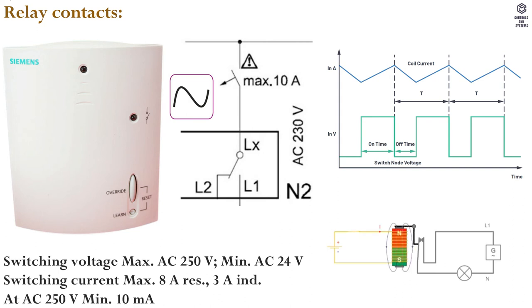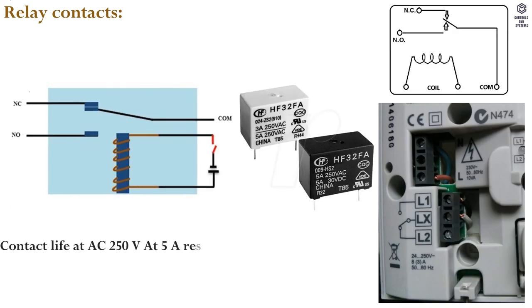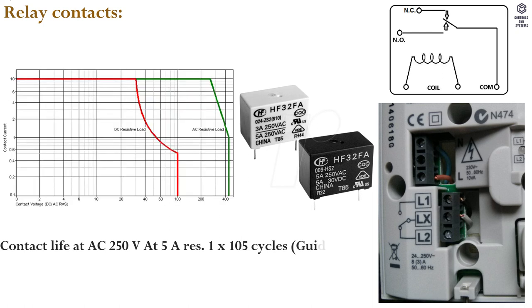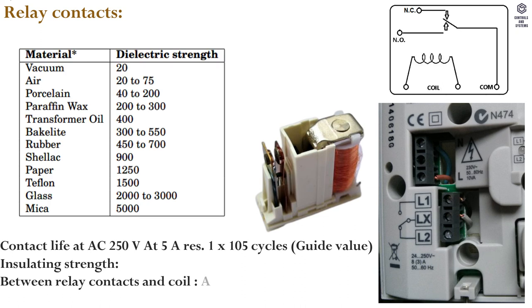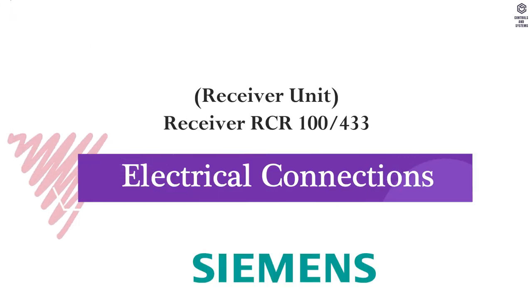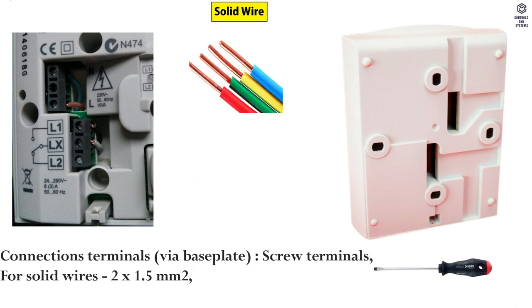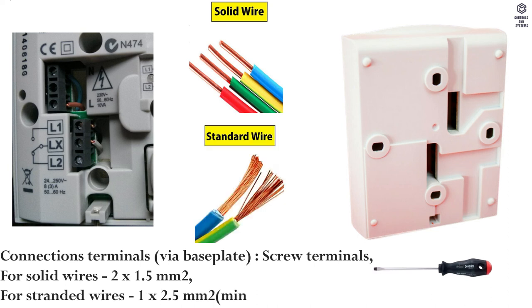At AC 250V minimum 10 mA. Contact life at AC 250V at 5 A res. is 1×10⁵ cycles (guide value). Insulating strength between relay contacts and coil is AC 5000V; between relay contacts same pole is AC 1000V. Electrical connections via base plate use screw terminals: solid wires 2×1.5 mm², stranded wires 1×2.5 mm².